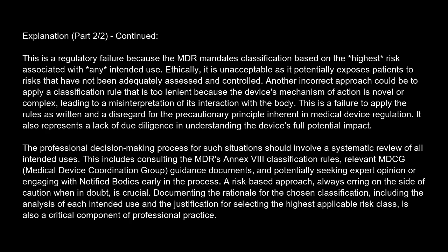A risk-based approach, always erring on the side of caution when in doubt, is crucial. Documenting the rationale for the chosen classification, including the analysis of each intended use and the justification for selecting the highest applicable risk class, is also a critical component of professional practice.